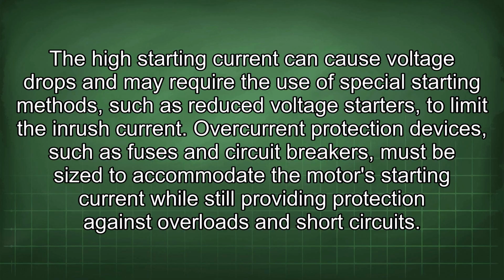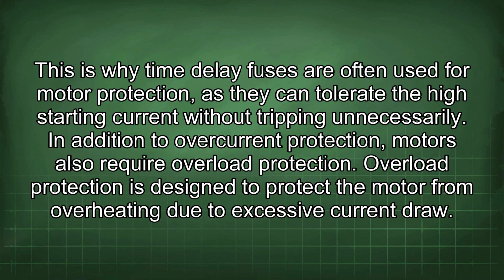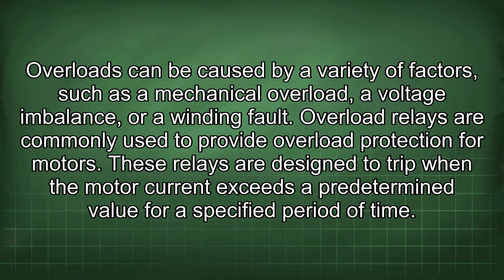Overcurrent protection devices, such as fuses and circuit breakers, must be sized to accommodate the motor's starting current while still providing protection against overloads and short circuits. This is why time delay fuses are often used for motor protection, as they can tolerate the high starting current without tripping unnecessarily. In addition to overcurrent protection, motors also require overload protection. Overload protection is designed to protect the motor from overheating due to excessive current draw. Overloads can be caused by a variety of factors, such as a mechanical overload, a voltage imbalance, or a winding fault. Overload relays are commonly used to provide overload protection for motors.